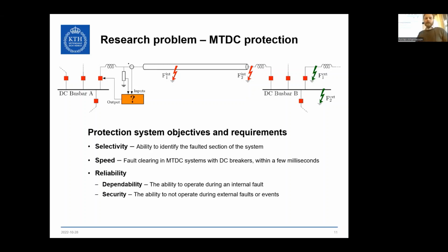So these two are always important to keep in the back of your mind, because if you try to optimize for one, you will always end up making the other worse. For example, if you put some logic in to block the protection, sure, you increase security, but dependability could be sacrificed, because that same logic could prevent the protection from actually operating when it should.